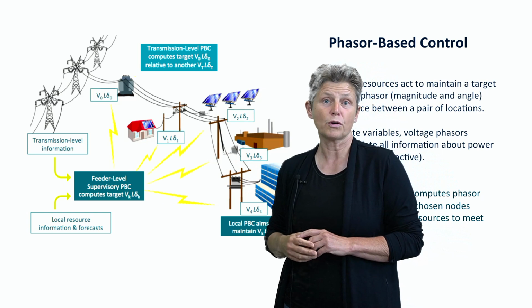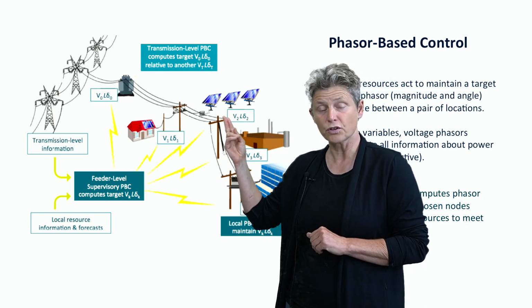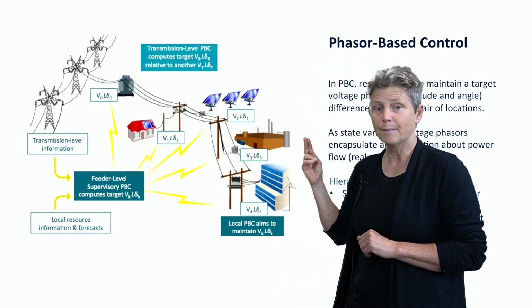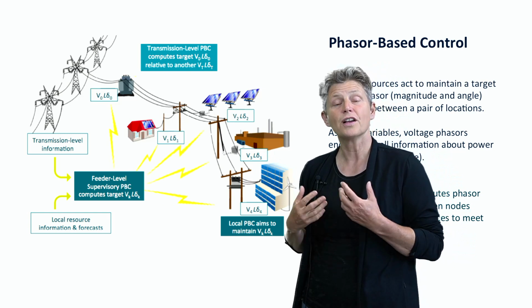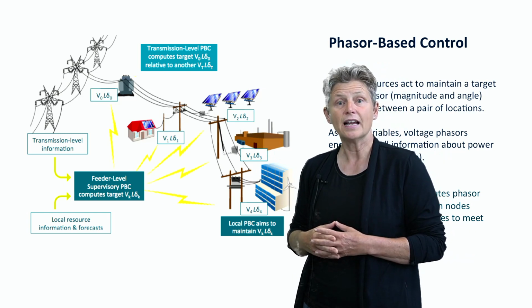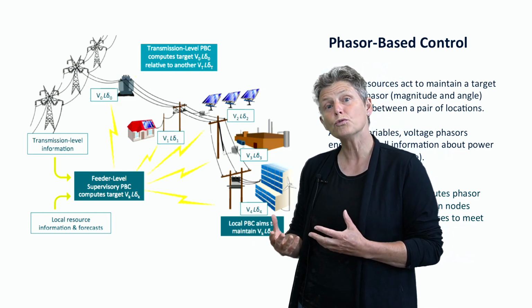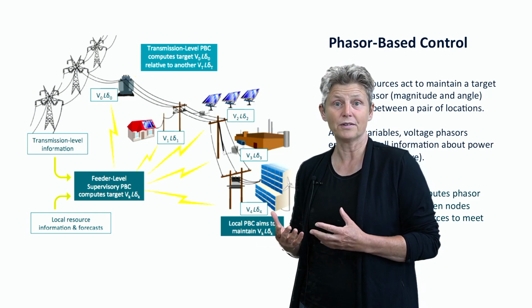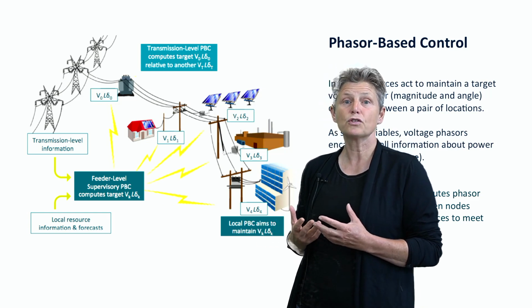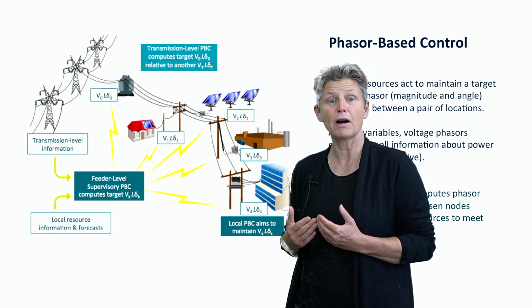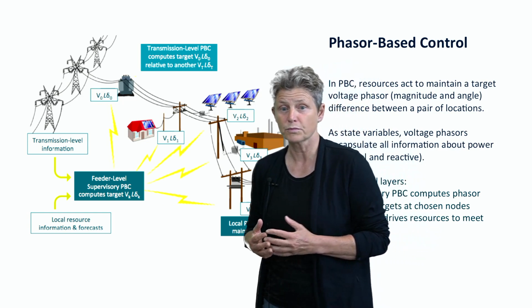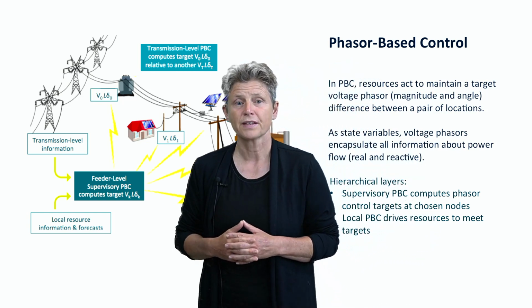The local controllers will then talk to the solar inverters, the controllable loads, the batteries, and recruit them to turn up or down depending on what's needed to maintain the desired power flow profile in terms of those phasors.